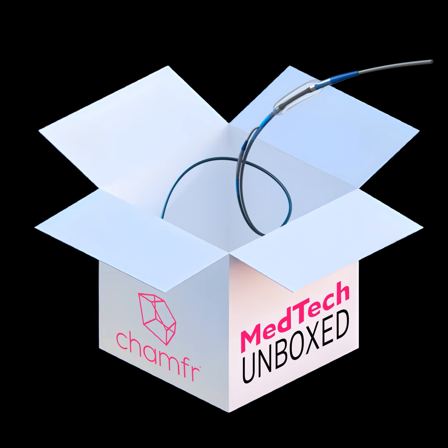So the PTFE or the braid laser hypotube coil kind of sit on top of the PTFE. So it's kind of like the body on frame design, like a pickup truck. So with the newer technology, like the one that we mentioned with EverGlide Plus, because it's a nylon 12 base liner, it is actually the same family as the jacket. They're all PA family based. And nylon, Pebax, they both stick pretty well to stainless steel. So it becomes more like a unibody design, like a car.